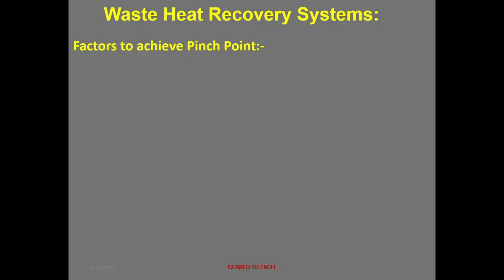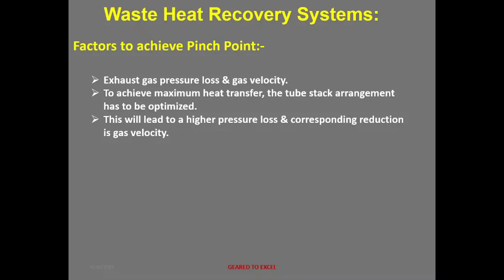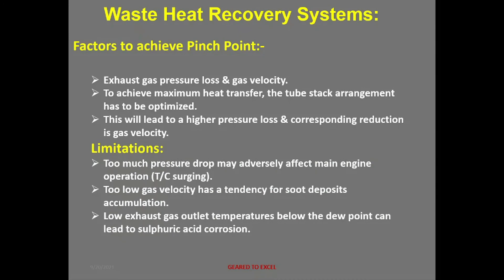Factors to achieve pinch point: for maximum heat transfer, the tube stack arrangement must be optimized, which leads to a higher pressure loss and corresponding reduction in gas velocity. Limitations include: too much pressure drop may adversely affect main engine operation, for example causing turbocharger surging; too low gas velocity causes soot deposit accumulation; and low exhaust gas outlet temperature below the dew point can lead to sulfuric acid corrosion. The dew point depends on sulfur content in the exhaust gas.